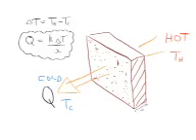In fact, the best insulators that are used in the built environment are things like the PUR and PIR, kind of proprietary foil-backed stiff foam boards that you see on building sites everywhere, made by companies like Kingspan, Celotex, Knauf and the like. They have thermal conductivities nudging towards 0.02 watts per Kelvin meter. So get that? The unit of the thermal conductivity of a material is watts per Kelvin meter.